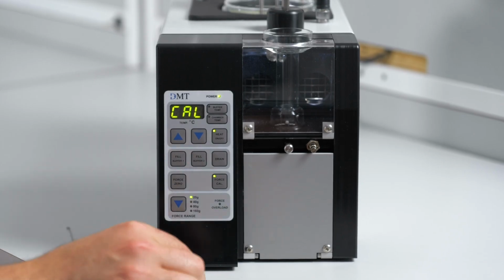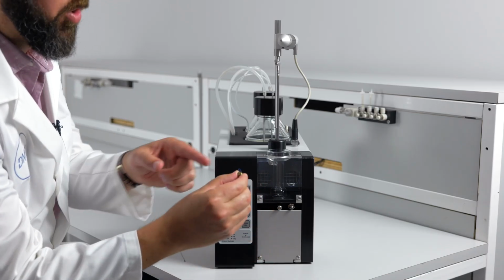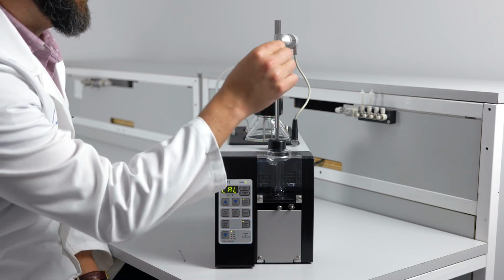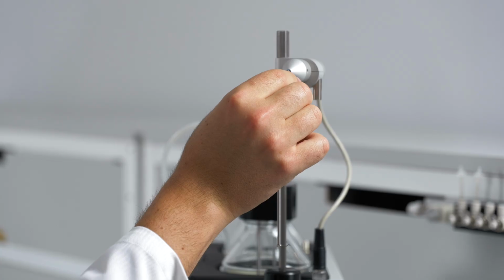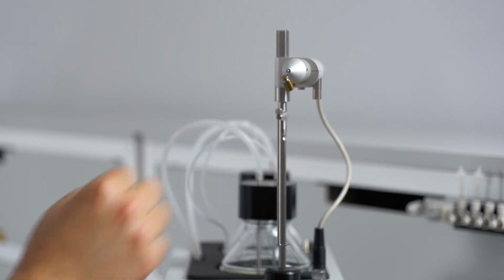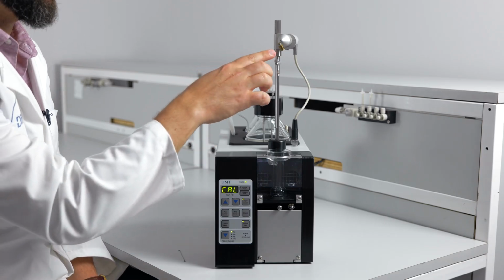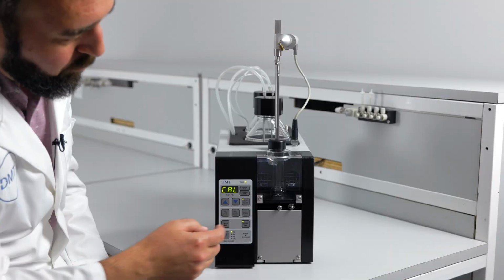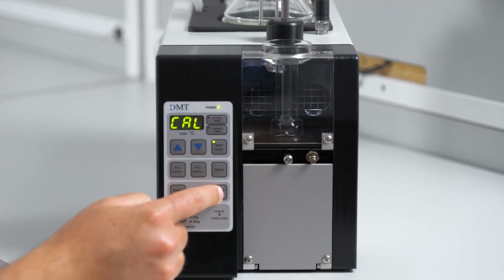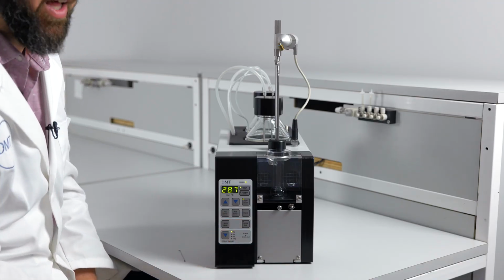At this point, we can take our 5-gram weight with the tie and hang it on the force transducer. Wait until it stops wiggling. After it is steady, press the force calibration button again, and the calibration is complete.